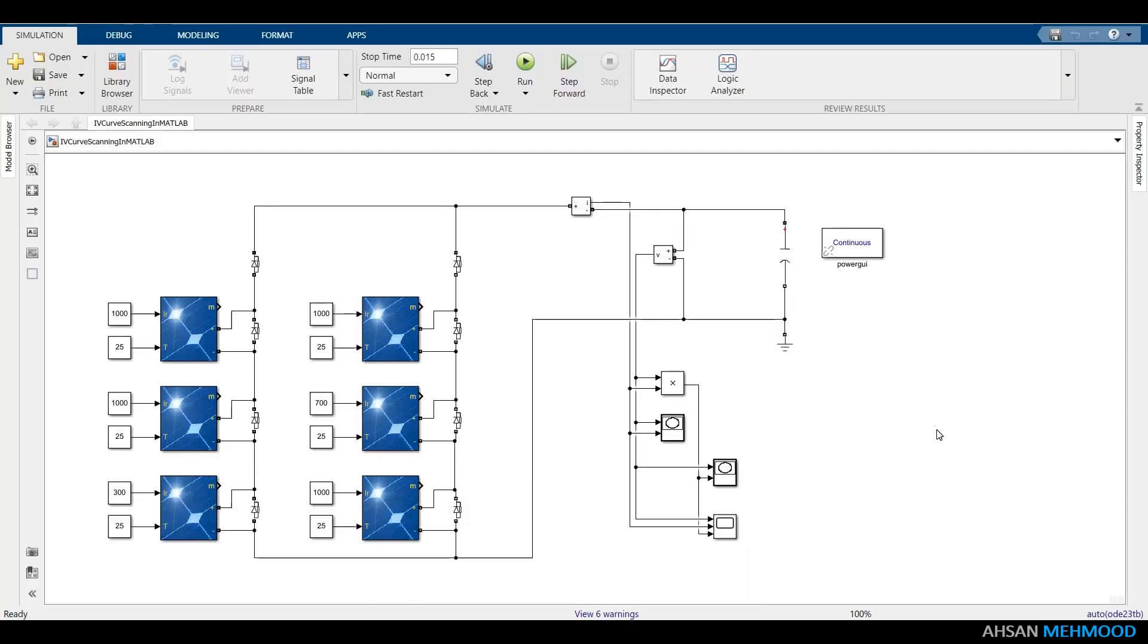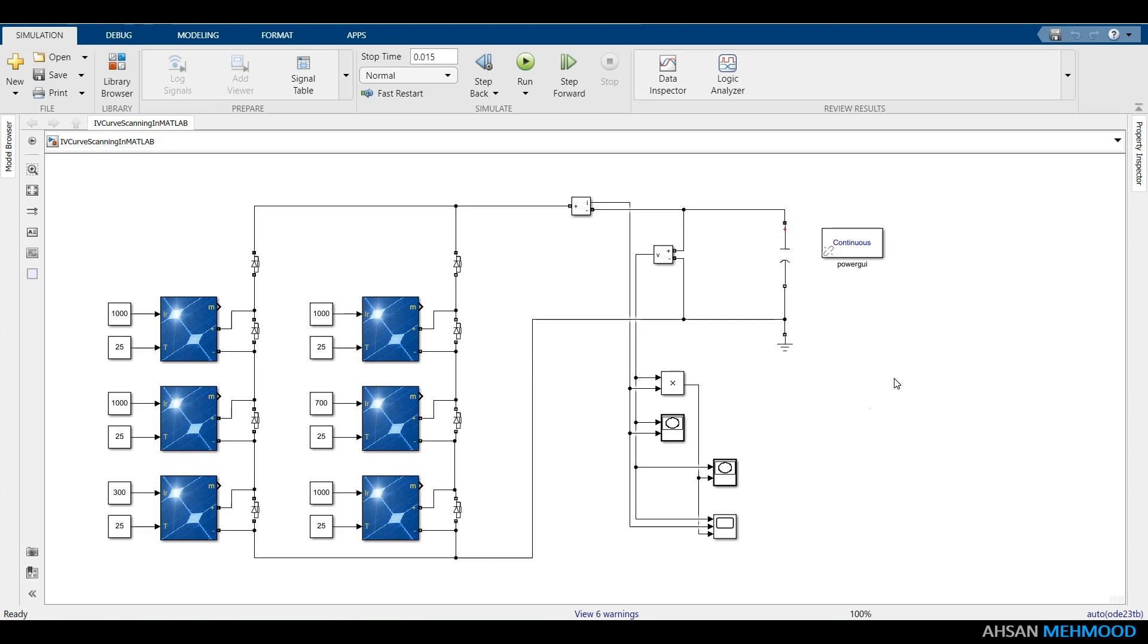Similarly, in this PV array, we may also create faults such as line-to-ground fault, line-to-line fault within a string, line-to-line fault between strings, open circuit fault and so on. It is important to recall that IV and PV curves display a staircase pattern and multiple power maxima for both partial shading and fault condition.